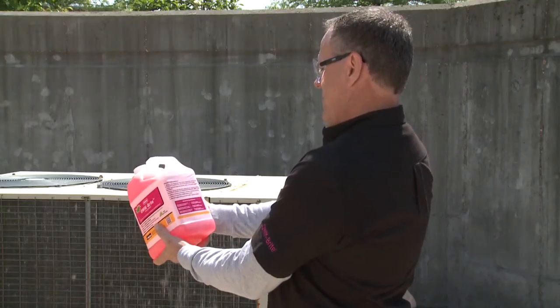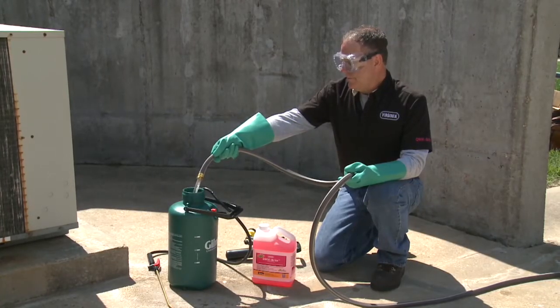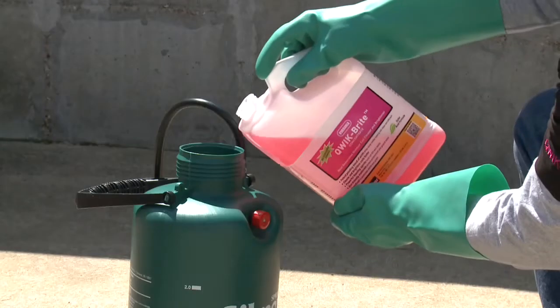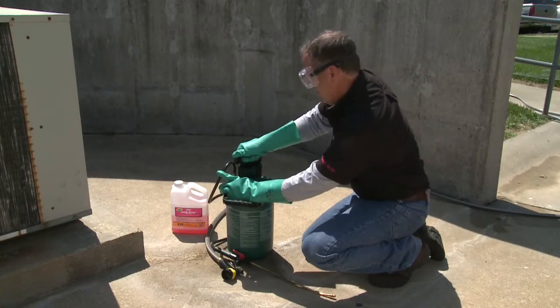Review coil cleaning requirements and choose the appropriate dilution level per the product label. For this application, using a two-gallon pump sprayer, mix one and a half gallons of water, followed by a half gallon of QWIK-Brite. Always add the chemical to the water. Now close and pressurize the sprayer.